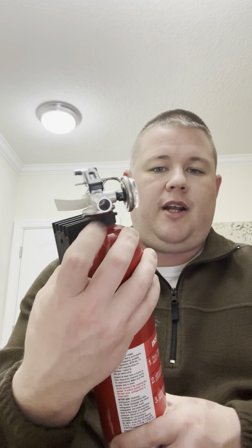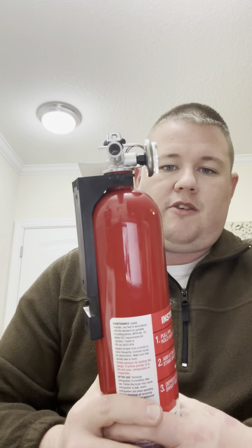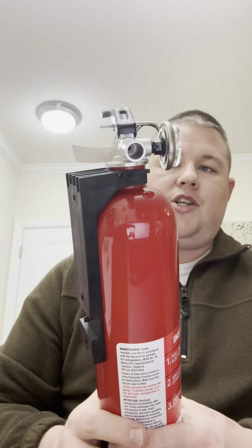As I mentioned, you've got the gauge there. You want to make sure that's in working order, not busted and beat up. You want to make sure there are no dents in the side of this that might have caused some kind of leak, which, if there was a leak, once again, you would see it right here on this little gauge. You want to make sure the nozzle point here is free of any obstructions. There's nothing inside that's going to prevent the flow of that chemical agent from coming.